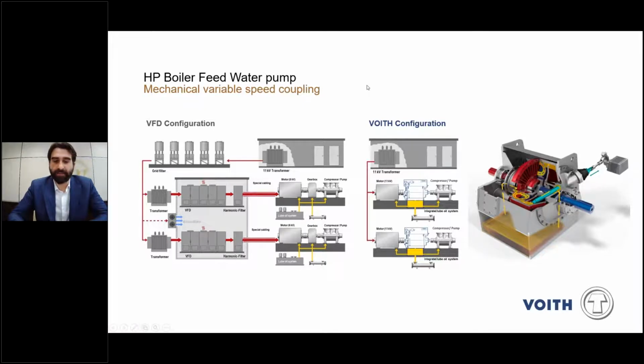Another system that TMP can supply in order to change the speed of the pump is the variable frequency drive. In this case, the VFD can change, by means of its electronics, the speed of the motor and the speed of the pump, changing the frequency of the supply tension to the electric motor. Both systems, however, have pros and cons, and their selection is often made according to the specific requirements of the customers. Anyway, TMP can supply both solutions as well.